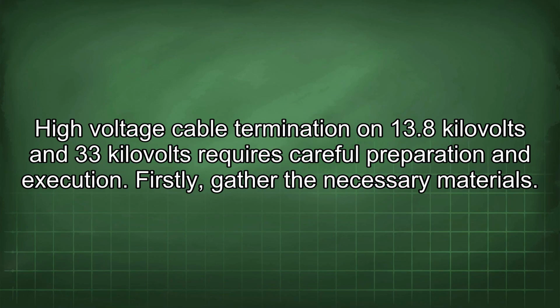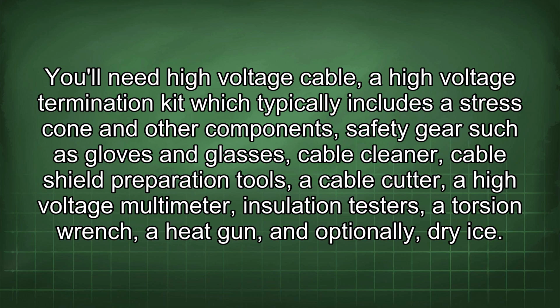High voltage cable termination on 13.8 kilovolts and 33 kilovolts requires careful preparation and execution. Firstly, gather the necessary materials. You will need high voltage cable, a high voltage termination kit which typically includes a stress cone and other components, safety gear such as gloves and glasses, cable cleaner, cable shield preparation tools, a cable cutter, a high voltage multimeter, insulation testers, a torsion wrench, a heat gun, and optionally, dry ice.